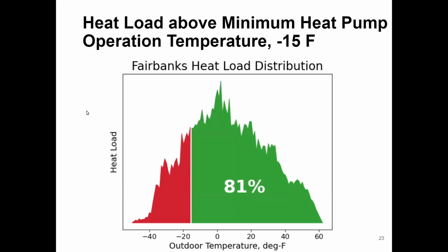A similar analysis can be done with the minimum temperature at which the heat pump works. Here's a calculation showing how, if you have a heat pump that only works down to minus 15, here's how much heat load you could take care of with that heat pump. This isn't an economic analysis — this is an analysis of how much of your heat load you could realistically expect to take care of with a heat pump that only operates down to minus 15°F.